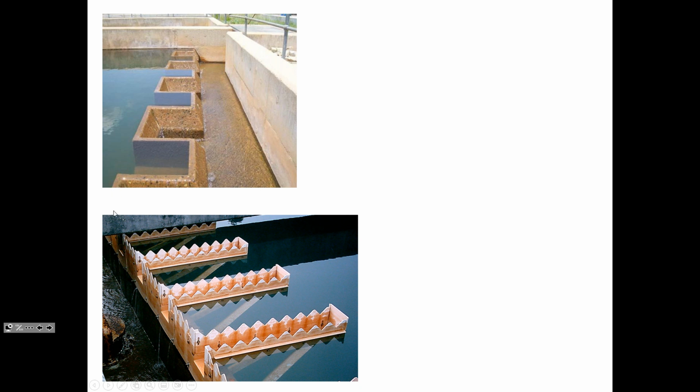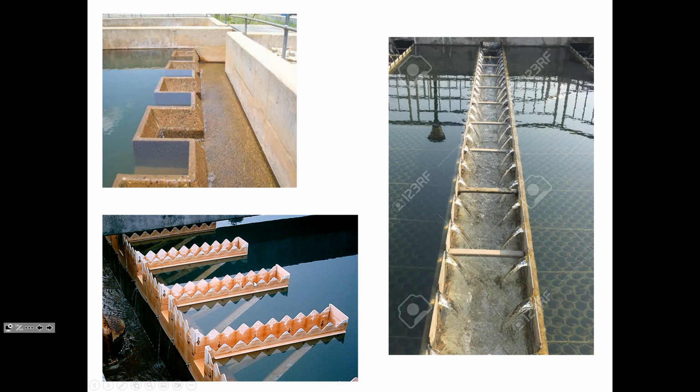And so here's another way of increasing the length of the launder when you have a fixed linear width at the end of the settling basin. If that's not enough, then you could increase the distribution of where the water's going out by protruding into the flow a bit and having the launder on either side, and the water can exit at a lower velocity with the more area that you're spreading it out over. So here, we've got the water coming into a central trough from both sides.